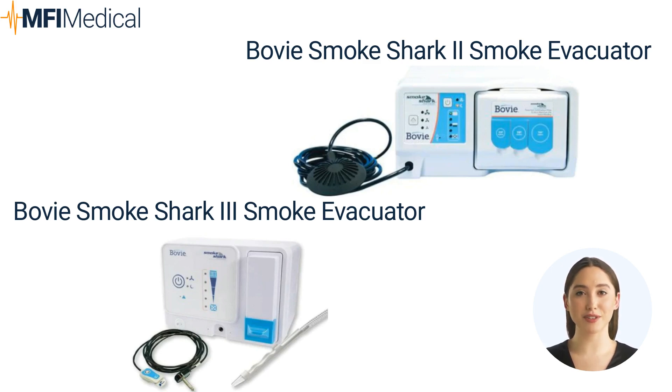The enclosed design of the filter ensures the safety of healthcare personnel during changes. The Bovie Smoke Shark III smoke evacuator is designed for shorter procedures lasting up to 15 minutes. It has a 6-hour filter that effectively removes 99.999% of 0.1–0.2 micron particles and microorganisms. Its compact and quiet design allows for wall-mounted installation in offices. With the Shark Skin Evacuation Pencil Adapter, it can be used with most pencils, reducing the biological and chemical risks associated with smoke from electrosurgery procedures. This device offers a streamlined design and user-friendly features, providing effective surgical smoke removal with optimal safety and quality.